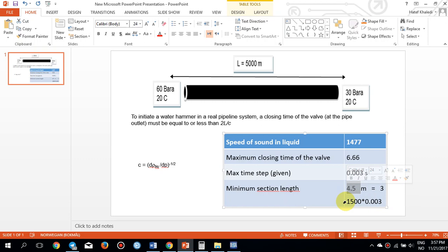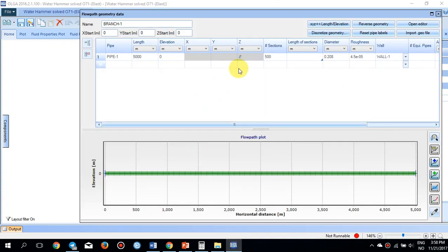If the section length is smaller than 4.5 meters with a maximum time step of 0.003 seconds, you may not capture the pressure wave in each pipe section. The sections used in this simulation are 10 meters each — 500 sections totaling 5,000 meters — which ensures the pressure propagation is captured at every single section.